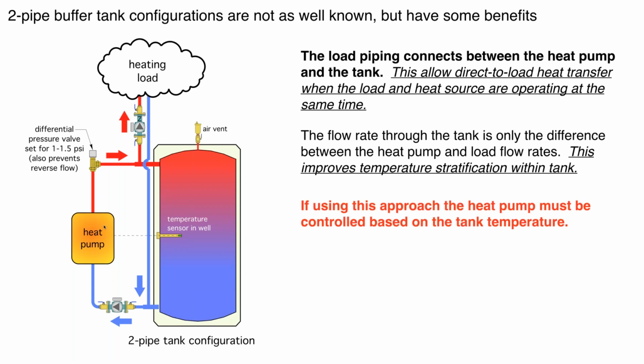So I want to drive home the point, if you're doing a two-pipe buffer tank, it is important that you're controlling the heat pump based on a temperature of the water in the buffer tank. We're not turning the heat pump on and off based on a thermostat that's out in the heated space. We're turning the heat pump on and off based on some kind of a temperature condition that we're trying to maintain in the buffer tank. It could be a set point with a differential. For example, it could be turn the heat pump on when the buffer tank drops to 95 degrees and then run it until the buffer tank gets up to 105.